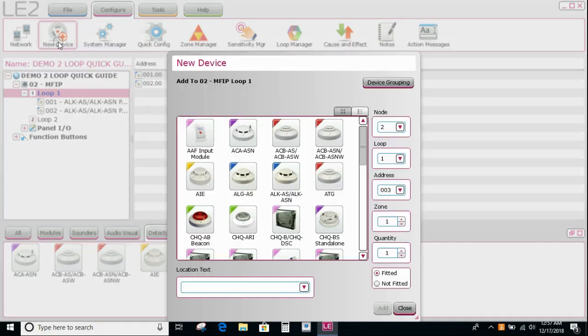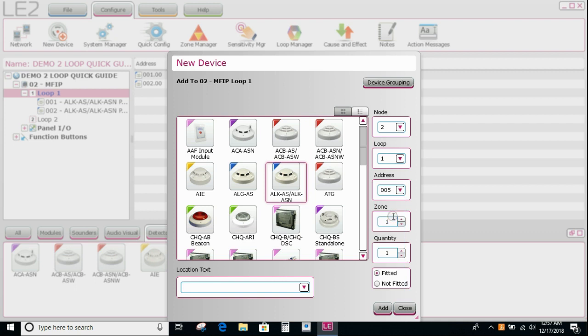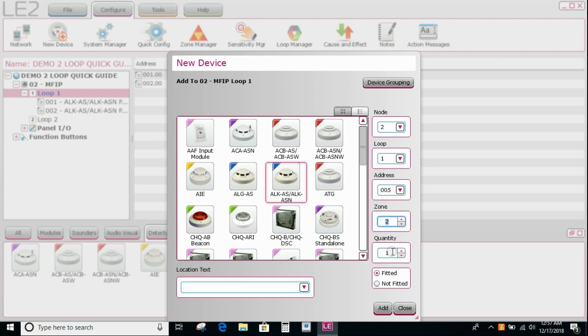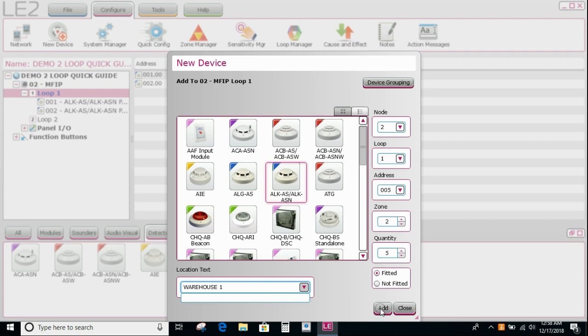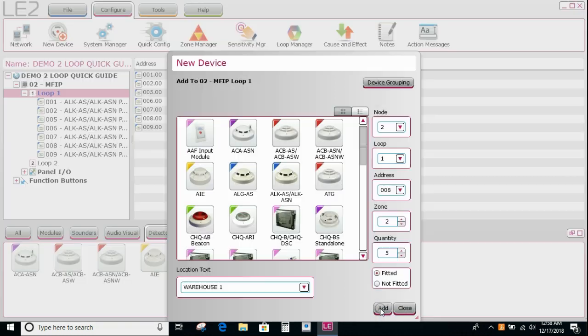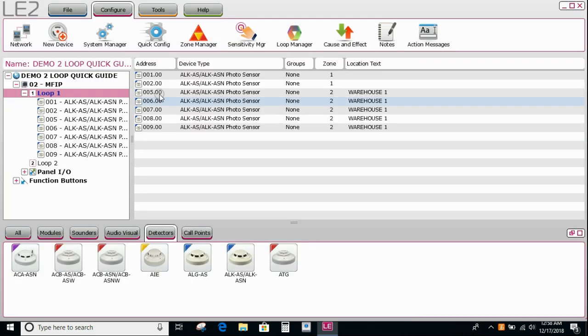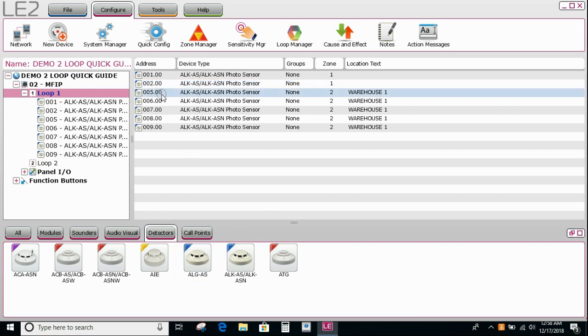Select the device that I want to add. Select the node and the loop it's going on. The address that they will start from, let's go from address five for this purpose. I might say they're all going into zone two. Quantity, I might say I'm going to add five of them. They're all going to be called warehouse one. And then I can select whether they're fitted or not fitted. If I select fitted, if they're not attached to the loop, the panel will show a disconnected fault. If I select not fitted and the detectors are not attached to the loop, it will not show up on the panel as a fault condition. I'm going to say add, close it. And you can see here these are the two that we added by the icons at the bottom, and these are the five that we added using the wizard.